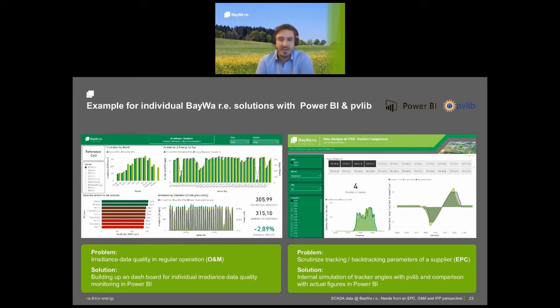Including also external data sources, and by that increasing the data quality of our sensors on site, because with this help, we were able to keep track of our data quality, whereas lots of the monitoring systems take care of alarm mechanisms for inverters and so on. We have incorporated something which can help us monitor the quality of our data with regards to irradiance. Lots of guarantees are linked to sufficient data quality of irradiance sensors.